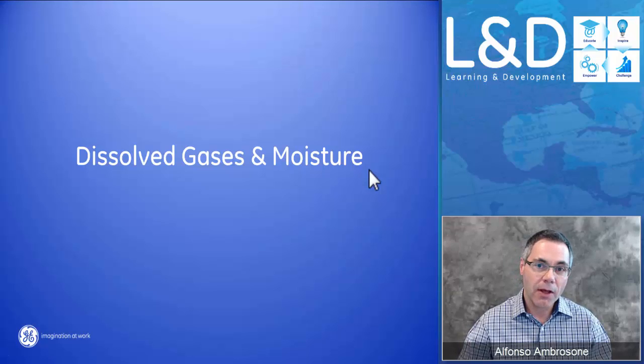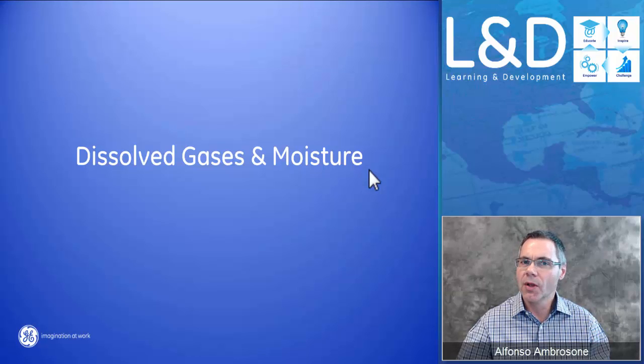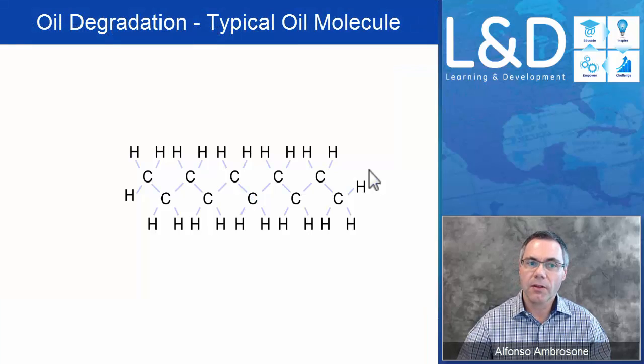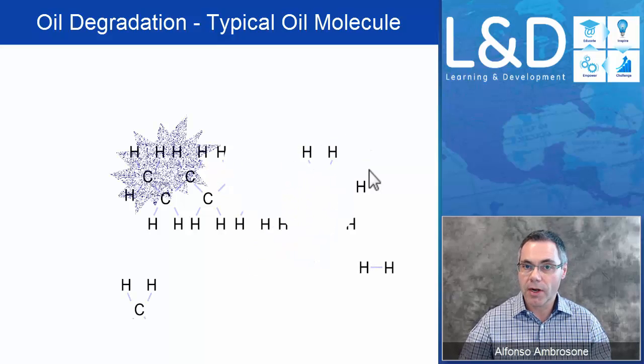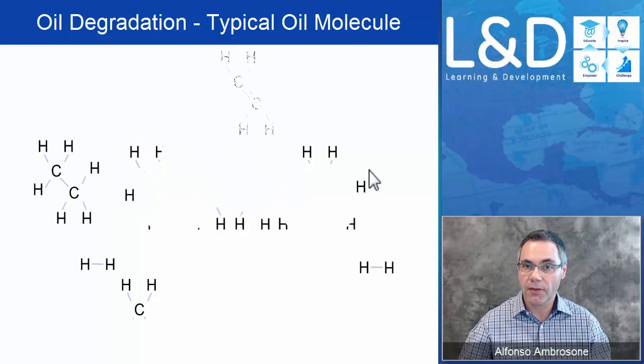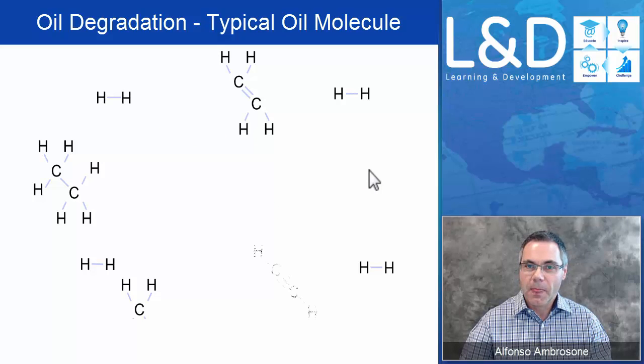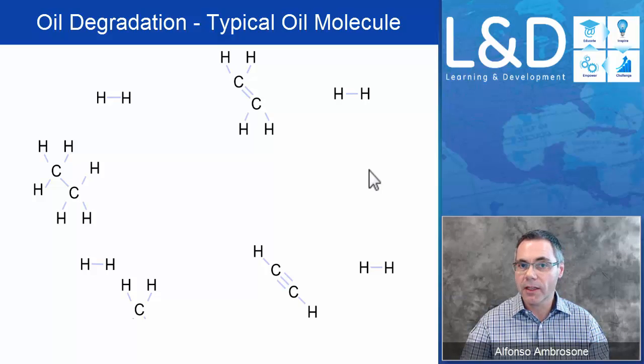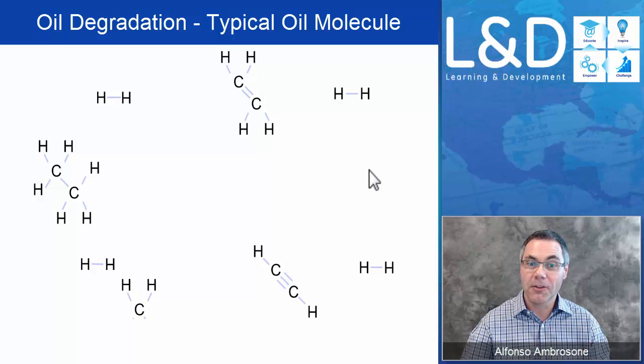Before we talk about the monitors themselves, I want to briefly touch on dissolved gases and moisture, because many people wonder where the gases or moisture actually come from. This is a typical oil molecule. When this oil molecule degrades, it starts to break apart, and as it breaks apart, it produces gases — hydrocarbons: hydrogen, methane, ethylene, and acetylene. There's a lot of hydrogen molecules produced, so hydrogen is the primary gas developed when an oil molecule breaks down.